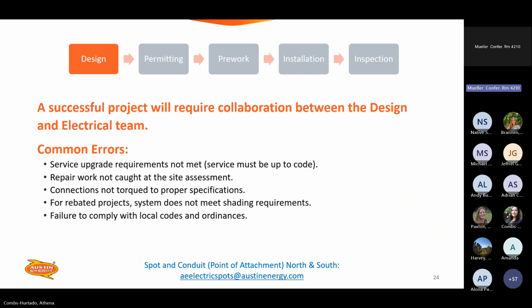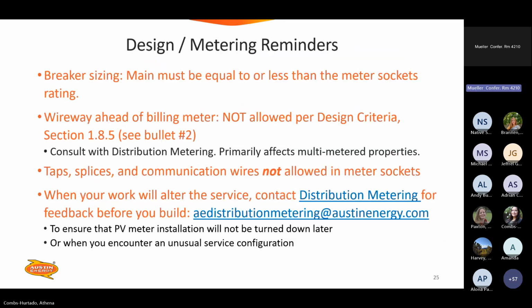A successful project requires collaboration between the design and the electrical team. Common errors: service upgrade requirements not met, repair work not caught at the site assessment, connections not torqued to proper specifications. You should be very careful about torquing things properly, especially in meter cans, because there's no access to those meters after the fact, and you should torque them with a properly calibrated torquing tool and mark them. For rebated projects, shade requirements not met is another, and of course, failure to comply with our local codes and ordinances. Questions about locations of meters and points of attachment, you can go to that email at the bottom there.